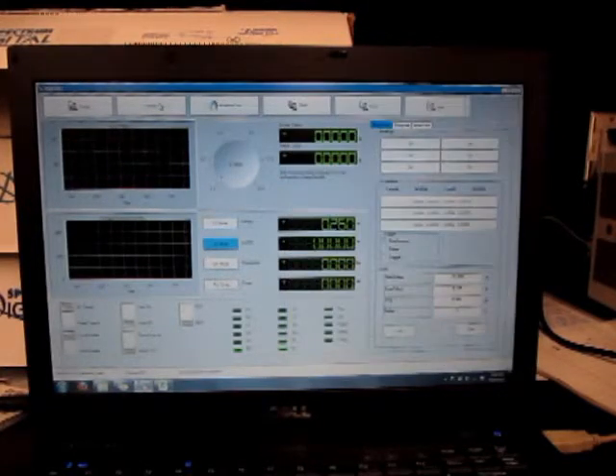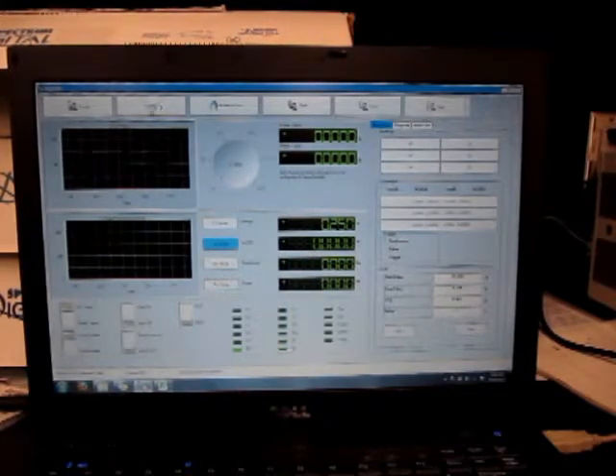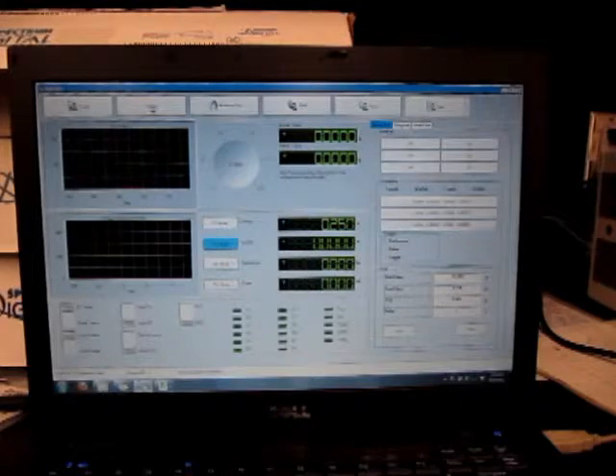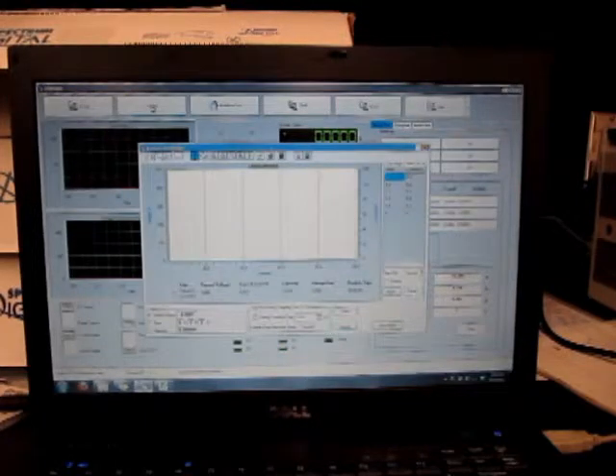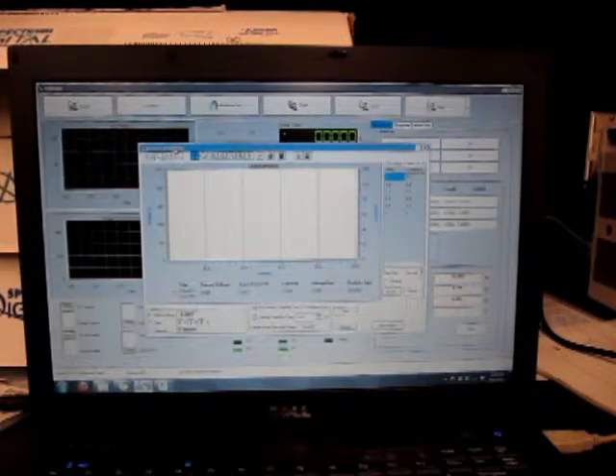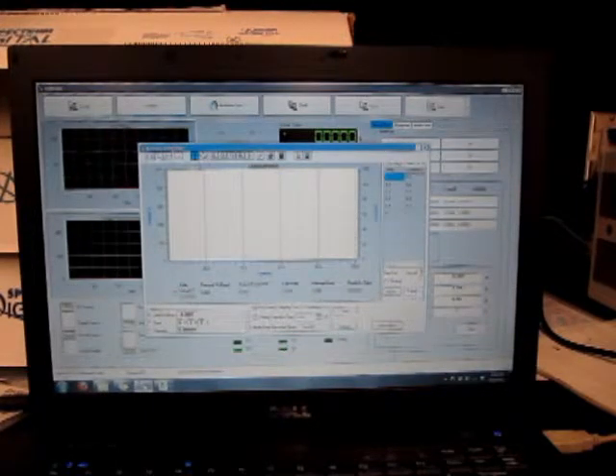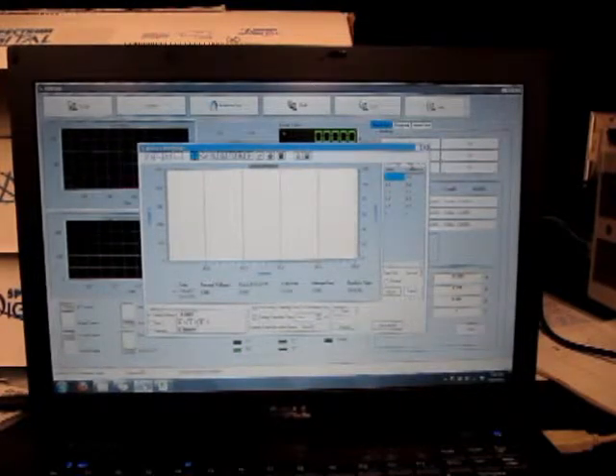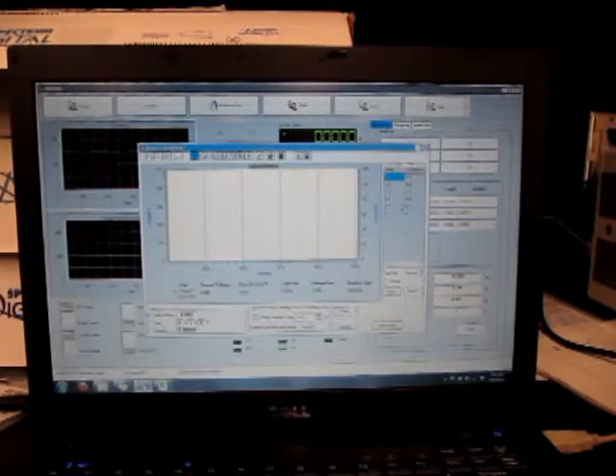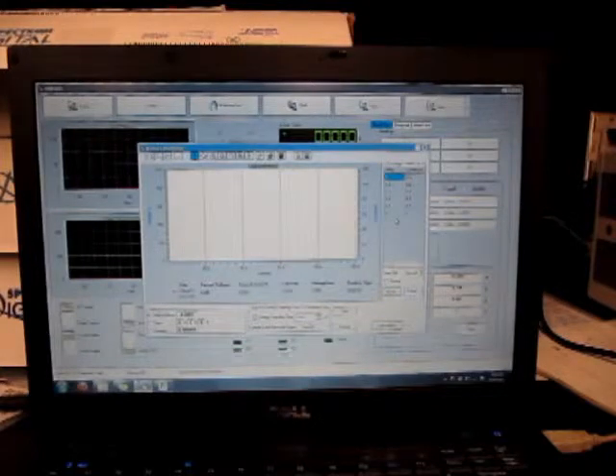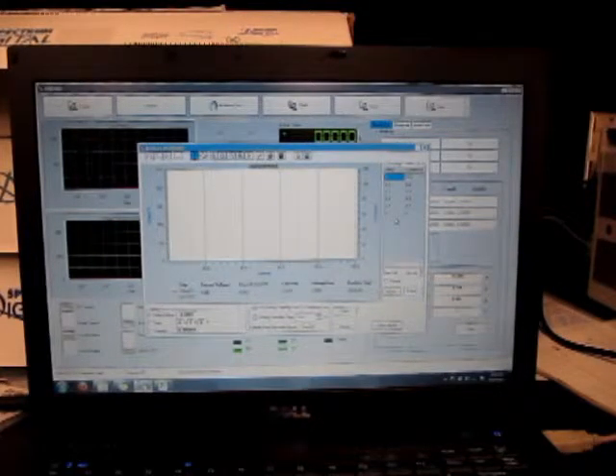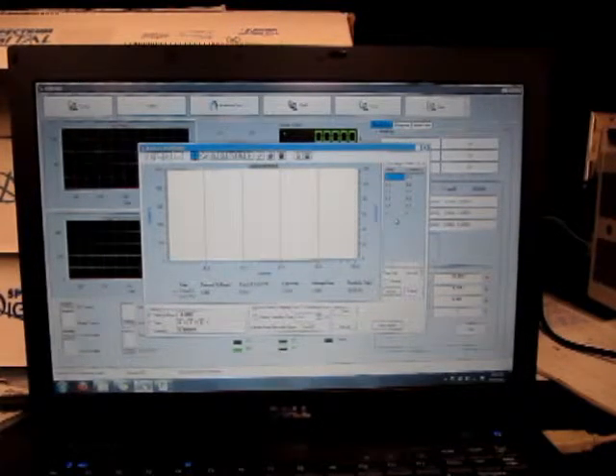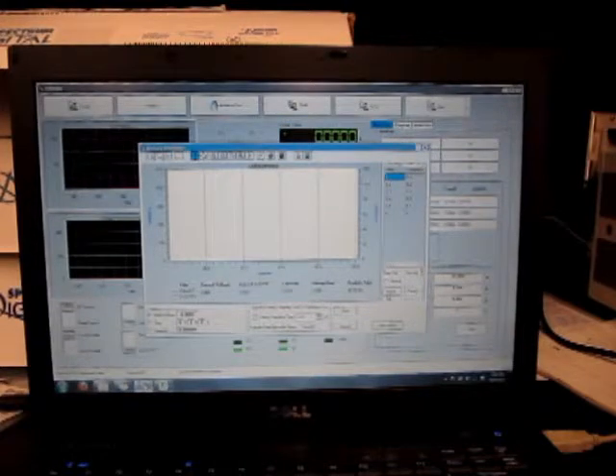So if we go to the top bar and click battery, then we come up with this battery discharge window. And our discharge current list is on the right. And we can either add manually more delays and current values or we can import a table from Excel.